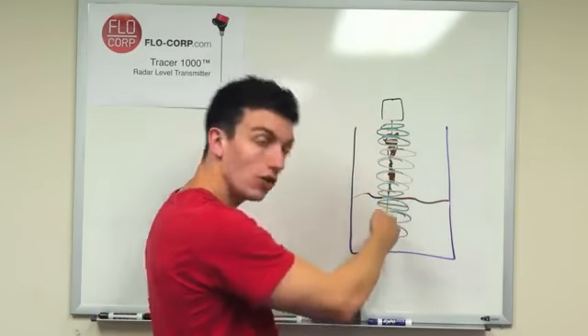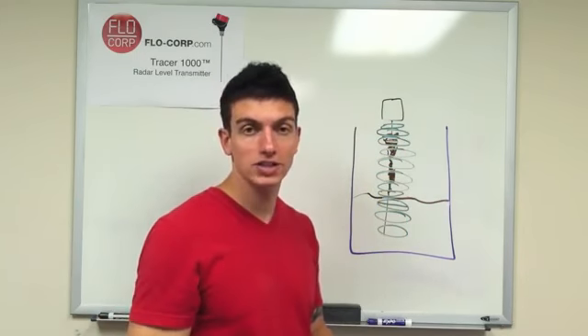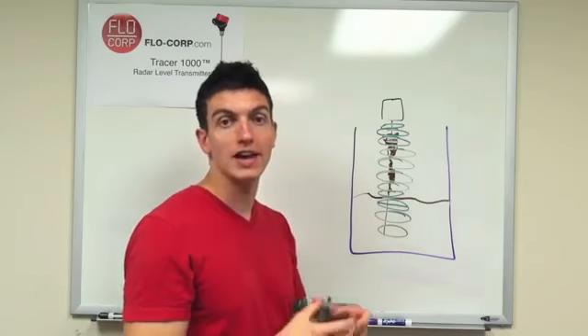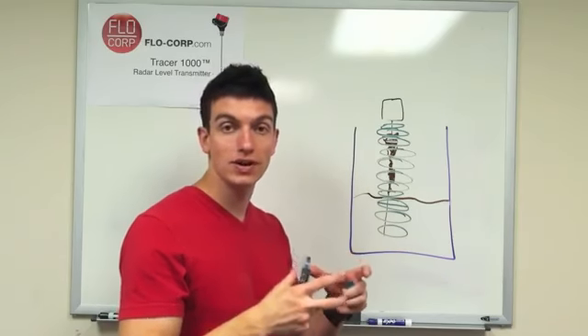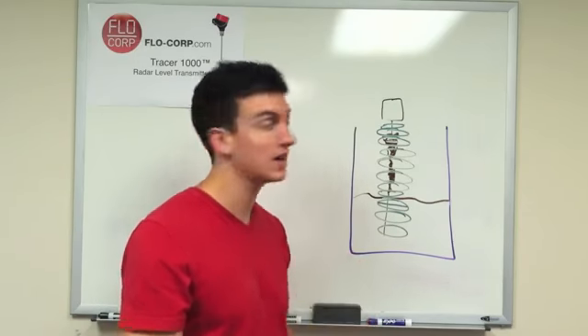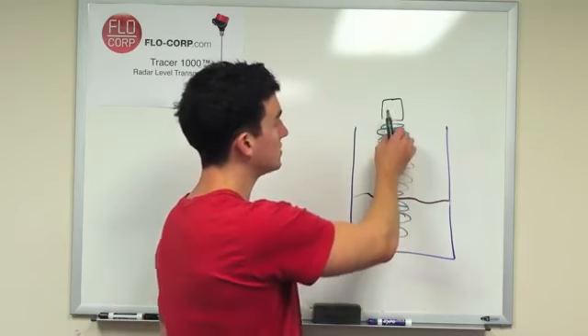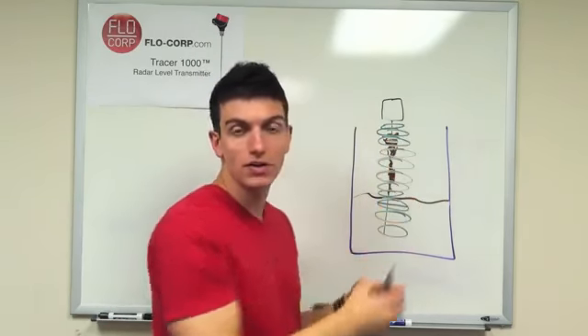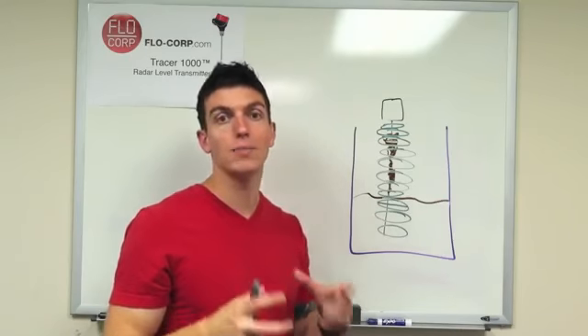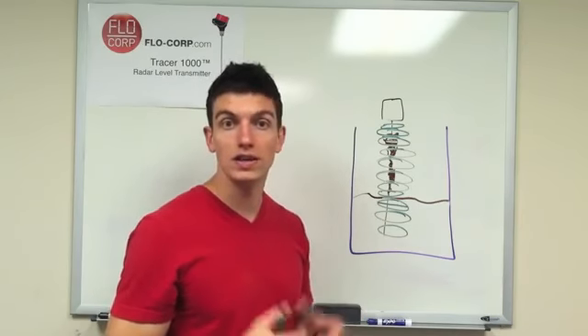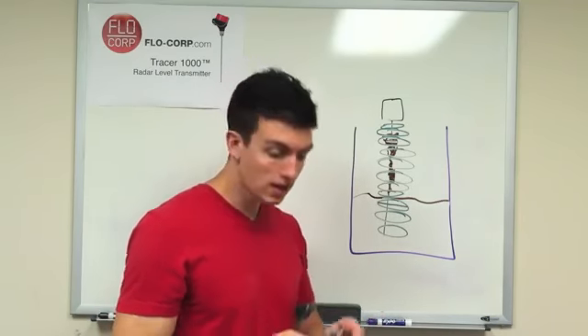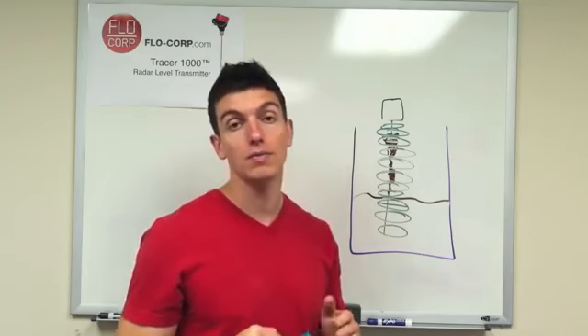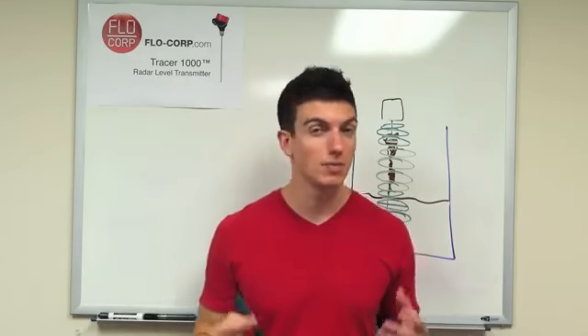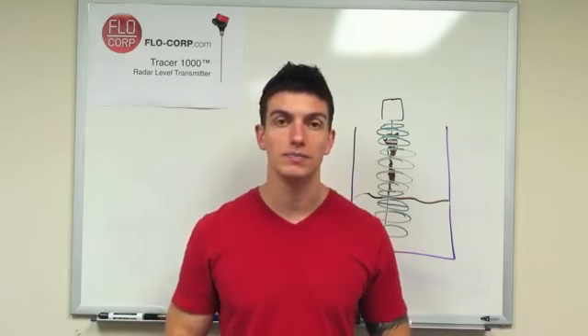Because it measures all the way to the bottom of the probe, it will actually get to the real liquid and translate that appropriate signal strength properly. And when it sends the signal back up into the meter, the artificial intelligence will properly calculate where the liquid level is. So emulsions are not actually a problem for some and probably most guided wave radar units.